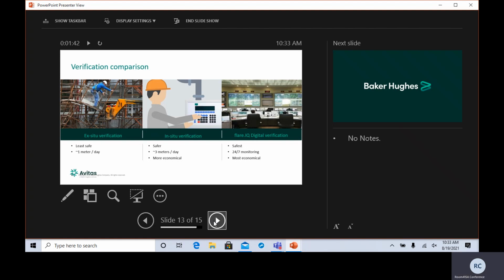You need to do it on your own, but in order to interpret the data, phone support is usually really good, but it gives you peace of mind to know that your flare meter is back online and operating as it should. But if you run 200 feet per second through a line, there's damage done somewhere to your line, whether it be just to a thermowell that's in place or possibly to our transducer. You never know what's going through the line. So, and Victor will go into a lot more into how we do that and how we're able to say that this is a legitimate verification according to the EPA.